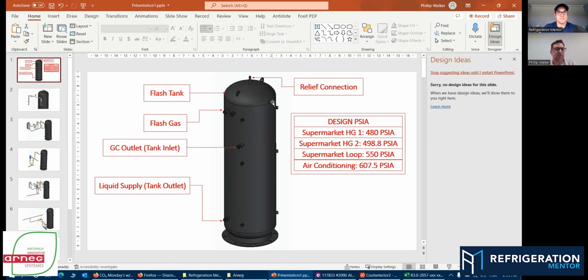So, guys, let's start talking flash tanks. We have customized our flash tanks for several years now. And just to let you know, not all manufacturers go to market the same way. I can only speak to how Arneg Systems is doing this presently. So all our flash tanks are rated for 750 PSI. So if using type L ACR Great Lakes copper, we're going to put a pressure relief on there of 650 PSI on the very top. And this flash tank is well protected.